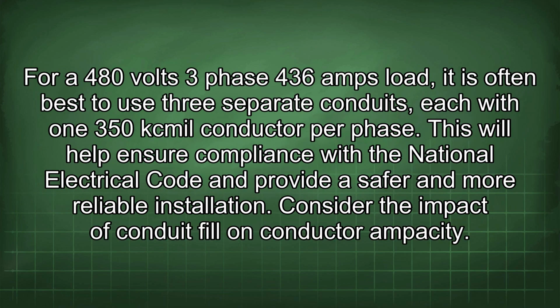For a 480 volts 3-phase 436 amps load, it is often best to use 3 separate conduits, each with 1 350 kcmil conductor per phase. This will help ensure compliance with the National Electrical Code and provide a safer and more reliable installation. Consider the impact of conduit fill on conductor ampacity.